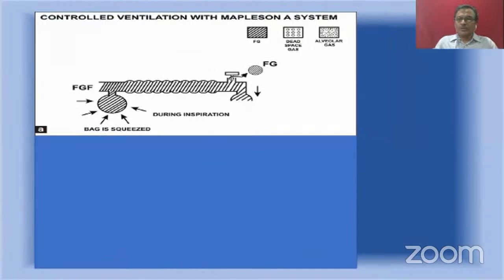Now, instead of spontaneous breathing, you are going to control the ventilation with a Mapleson system. What is going to happen? Look at this picture. See, this system is filled with the fresh gas and you are squeezing the bag. And when you squeeze the bag, look at the APL valve. Because here the APL valve is partially closed. It is not open as in the case of spontaneous breathing. It is partially closed, so you need a higher pressure to open it up. So when you squeeze the bag, a higher pressure is developed and you can see the fresh gas is escaping to the atmosphere and also going towards the patient. There's no confusion about that, right?